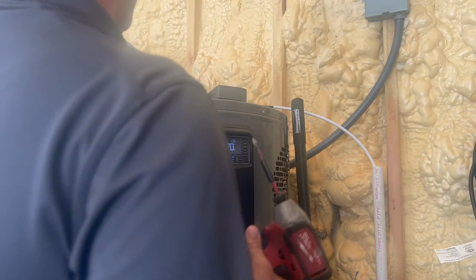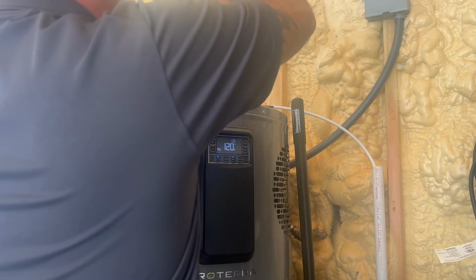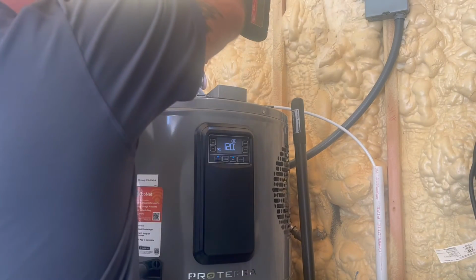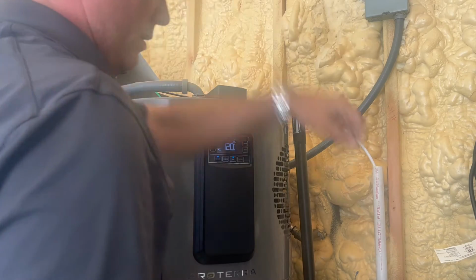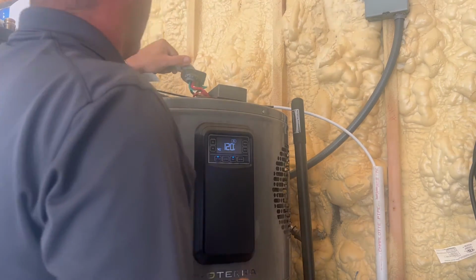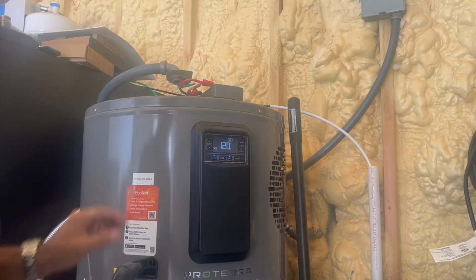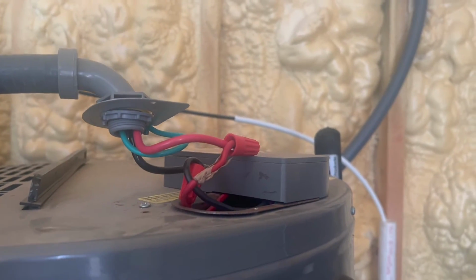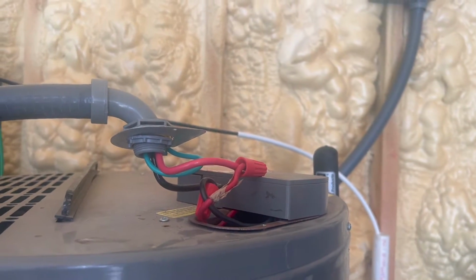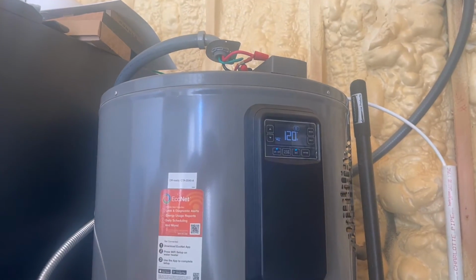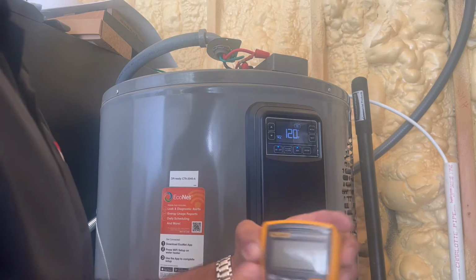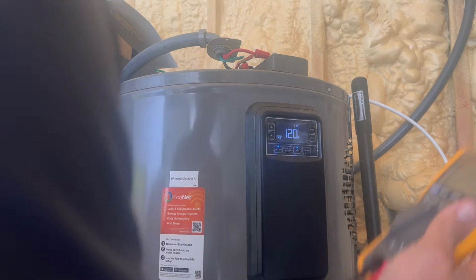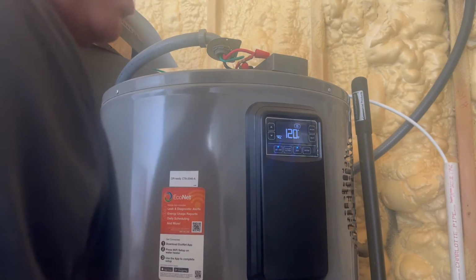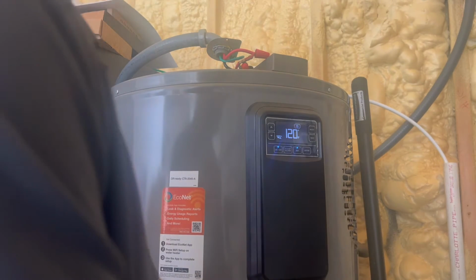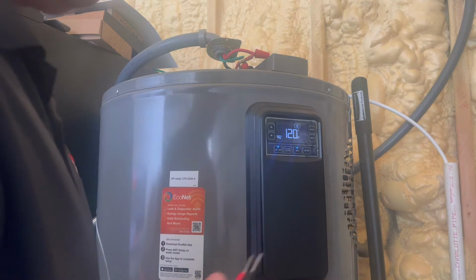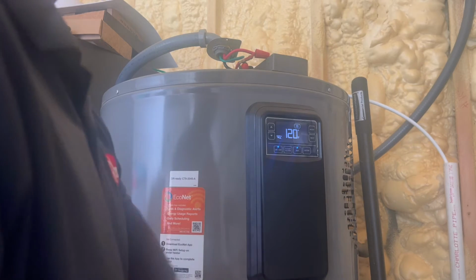Okay, let's just do a quick test up here. We'll start at the top, work our way down. Okay, so we can pull our top connection off and expose the two wire nuts that are in there. That's a great place to test from. You'll want to get your multimeter out and set that to alternating current. This is an auto ranging meter. If yours is not auto ranging, just set it to the one step higher than what you're testing. We're looking for 240 here. 208 to 240 is of course going to be what works for this heater. So if your meter has an option for 500 or 700, that's what you would set it at, not at 200. That would be too low.